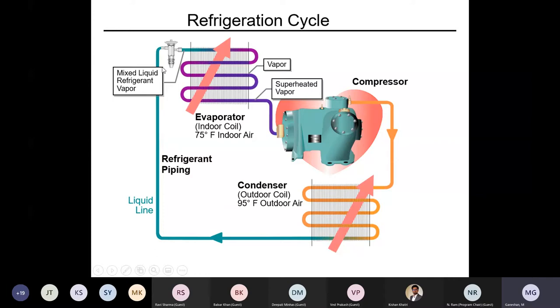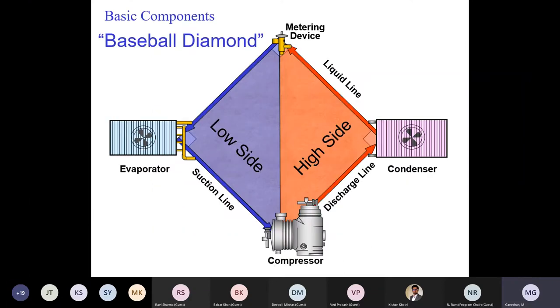Before the evaporator, it is high pressure liquid. Then when it passes through the expansion valve, it tries to change its state. Thereby the low temperature, low pressure refrigerant goes in, and it can absorb the heat in the evaporator, thereby doing the refrigeration. This is a simple saturated cycle now. If you see a baseball, we call it basically a baseball diamond. It's like a one-side system.